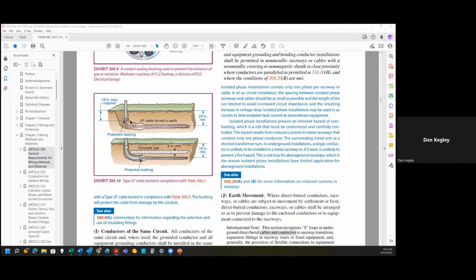And then that'll keep that moist air that's from the ground in that conduit. And if it does condense out, it'll just go back into the ground. But it won't condense out inside the box, causing corrosion on your connectors and fittings and that kind of thing. And then, of course, the bushing itself protects the wire as that wire gets moved around from the ground movement. It helps keep it from biting into the edge of that conduit, if you will. Right.